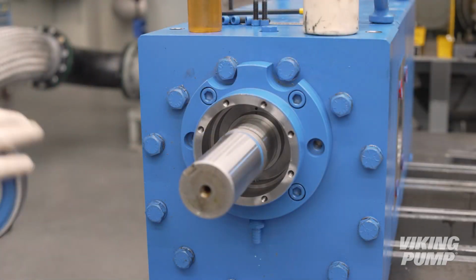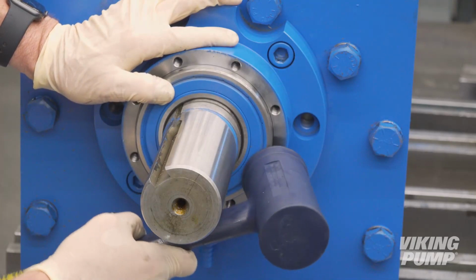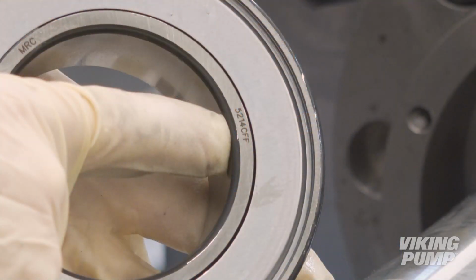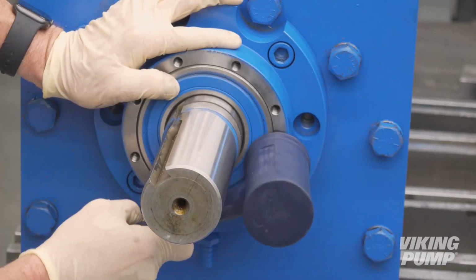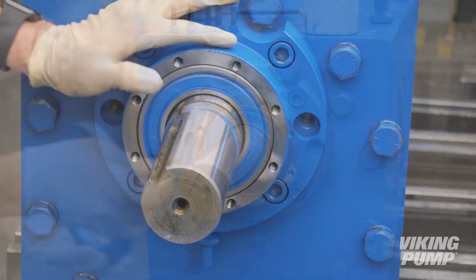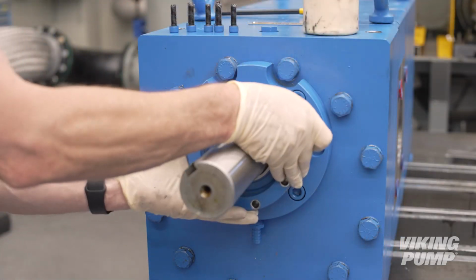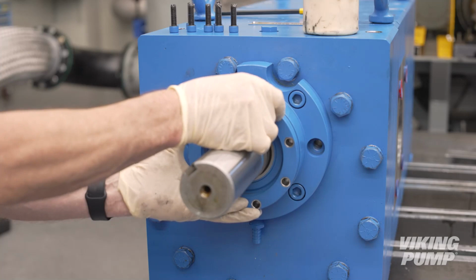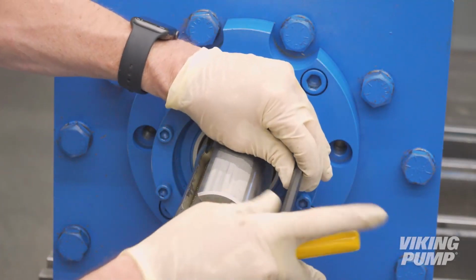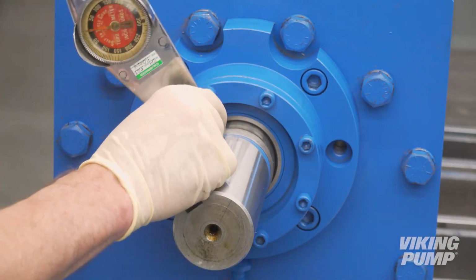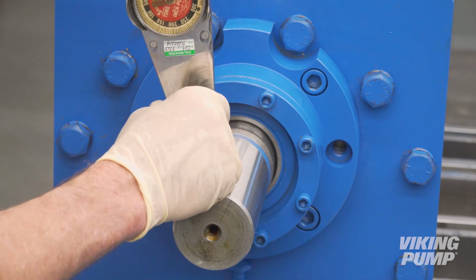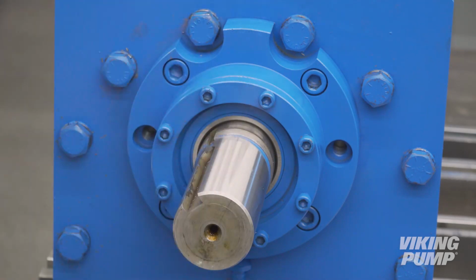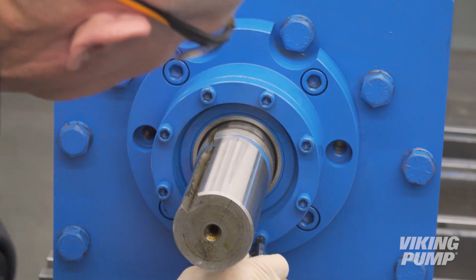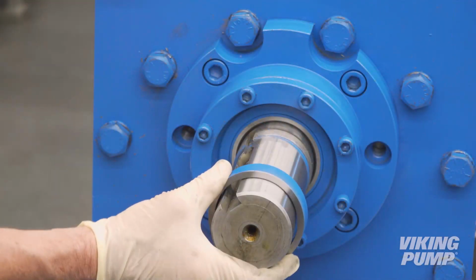Coat the thrust bearing in light oil and install onto the shaft. Make sure the printed letters on the outer race of the bearing are facing outward. Install the bearing end cap. Tighten the cap screws in a star pattern. Torque the seal holder cap screws and bearing end cap screws to the appropriate torque value. These values can be found in the technical service manual. Install the outer bearing spacer.